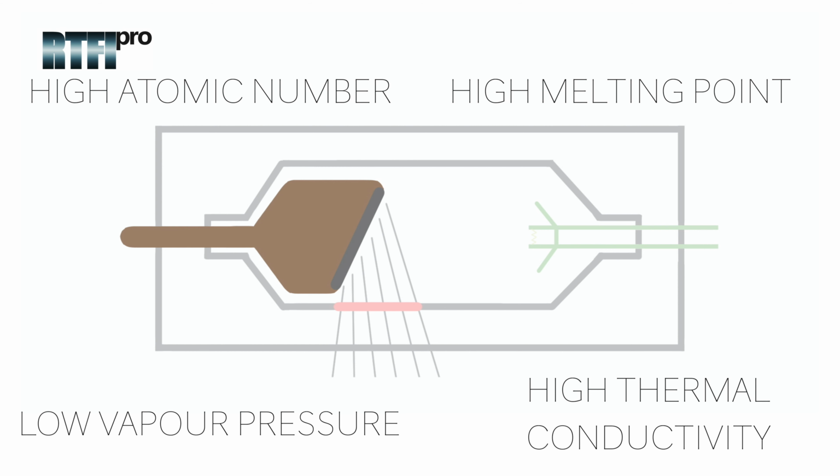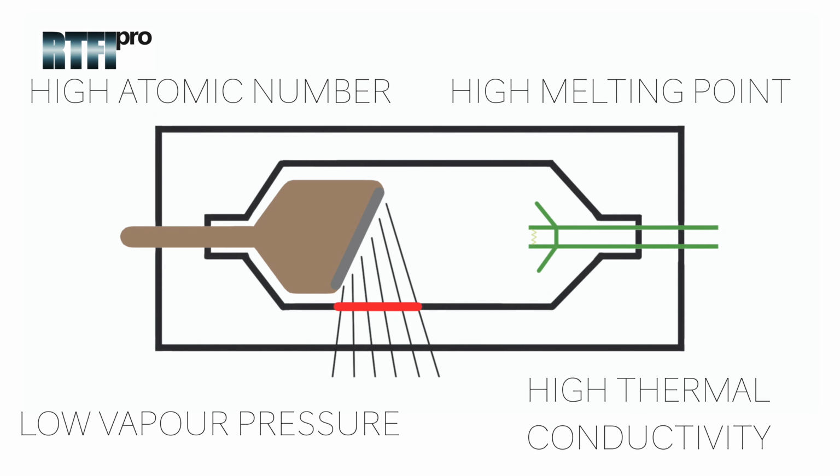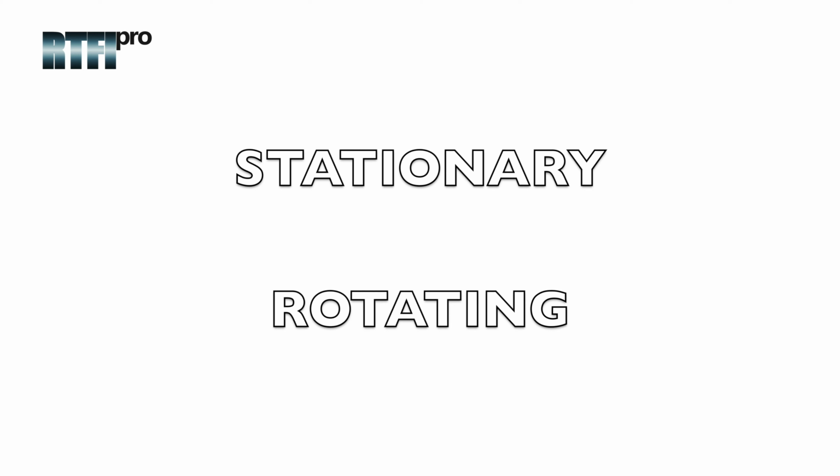In addition, the anode is attached to a copper stem, which is a good conductor of heat, as heat is impacted at the target. It is being dissipated efficiently from the tungsten anode and copper stem to prevent burnout of the machine. There are two types of anodes, a stationary anode and a rotating anode.